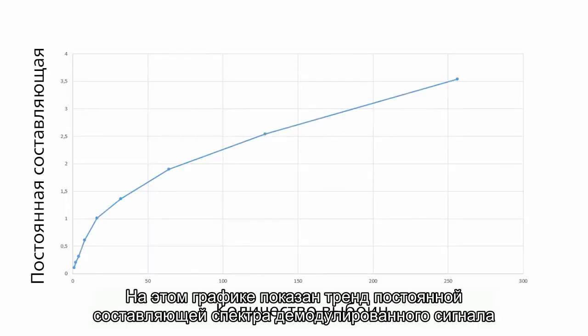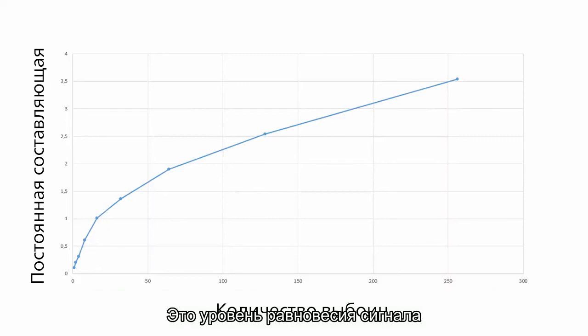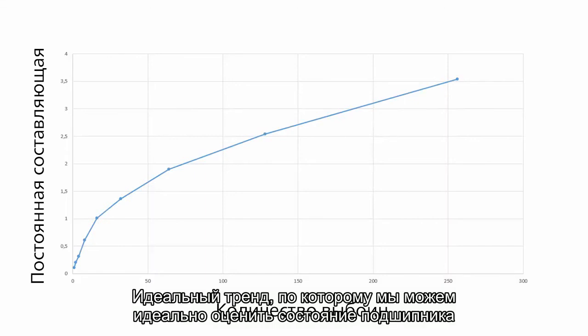This graph contains the trend of DC part of demodulation spectrum. It is the amplitude of line 0. And what we see? The perfect trend from which we can perfectly evaluate the bearing condition.